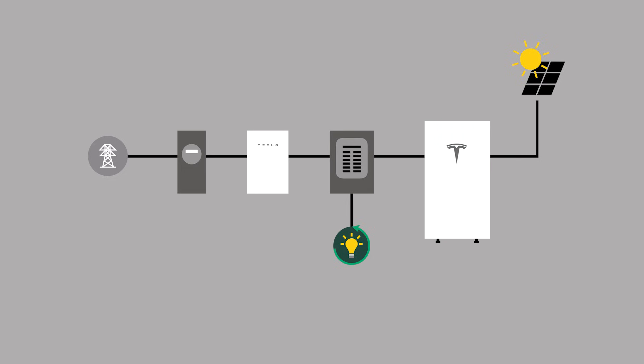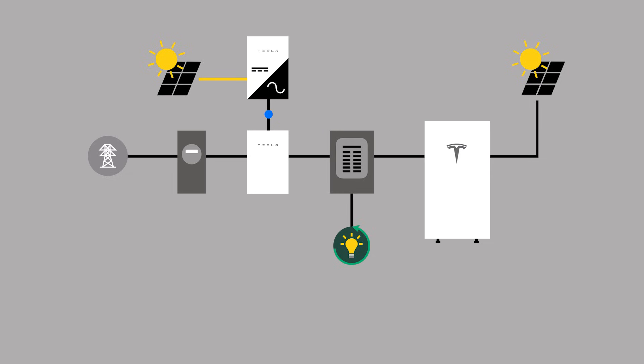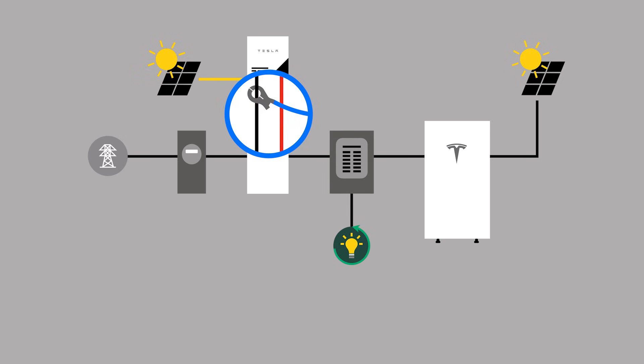On the other hand, any solar connected to an existing Tesla solar inverter, or third-party inverter, requires the use of an energy meter to monitor the inverter's AC output. A single CT is placed around one phase to monitor the AC output of the inverter.